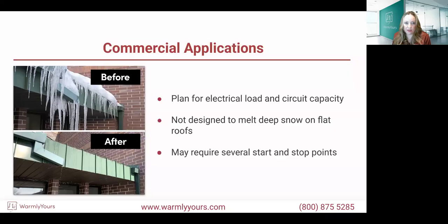So if you're looking for a product that's going to take the weight off of your building, this is not going to do that. May require several starts and stopping points. Sometimes, depending on the size and shape of the building, we may run 100 feet of cable, make a termination spot, start again with another cable somewhere else. Sometimes they can be connected to the same main control panel. They're going to run into a junction box, but we may need several starting and stopping points, depending on the large size of the application when you're talking about commercial projects.